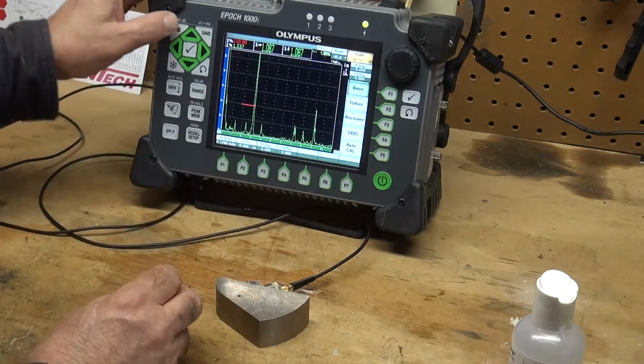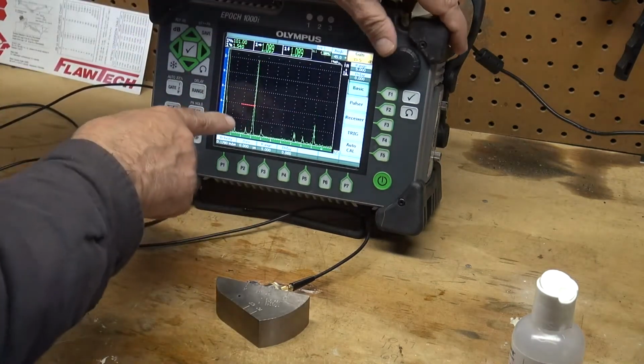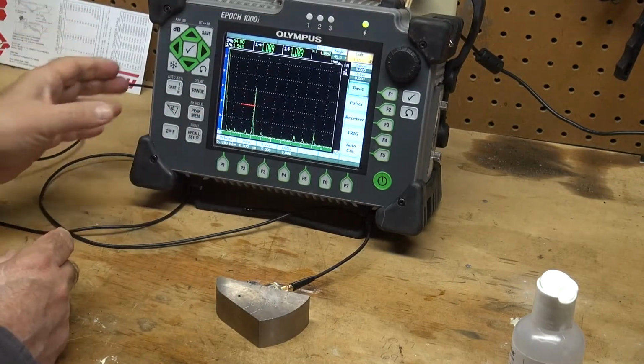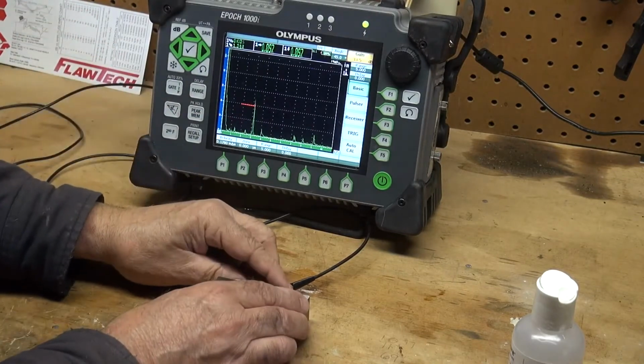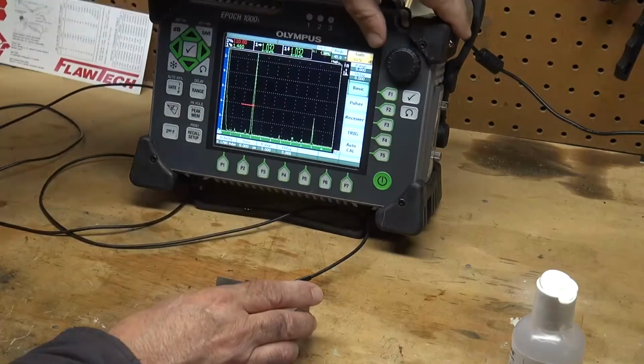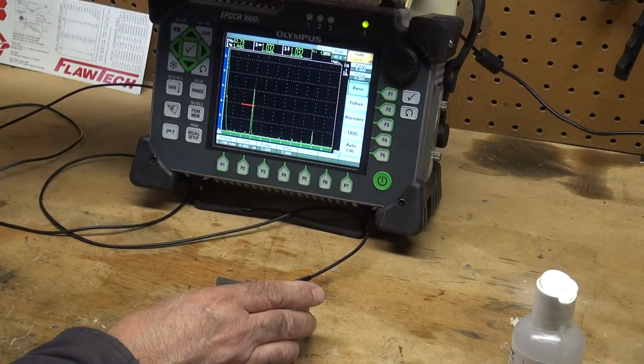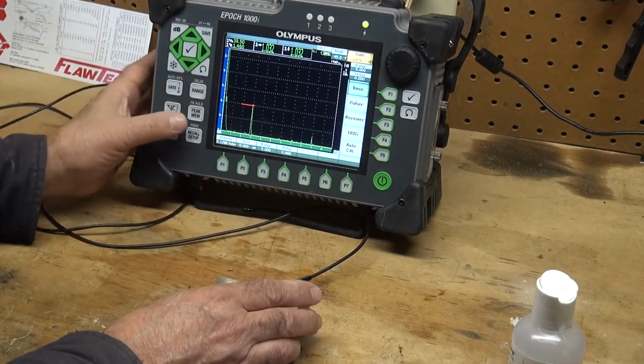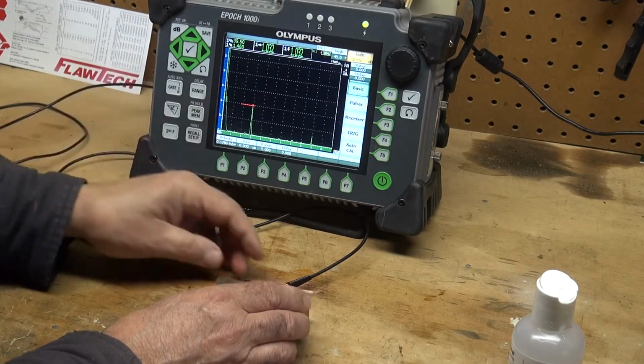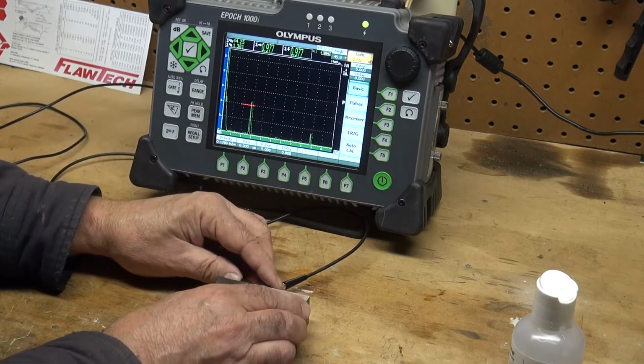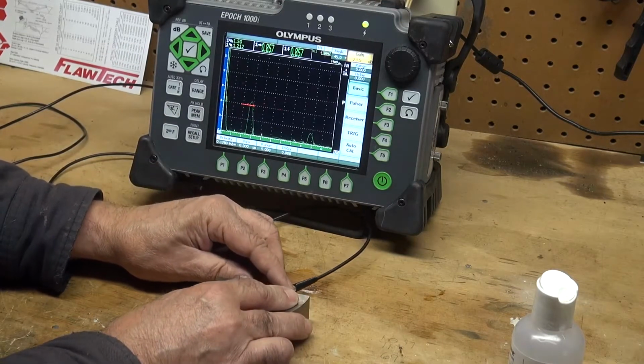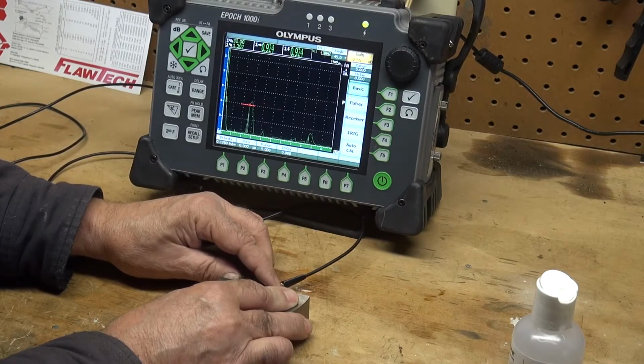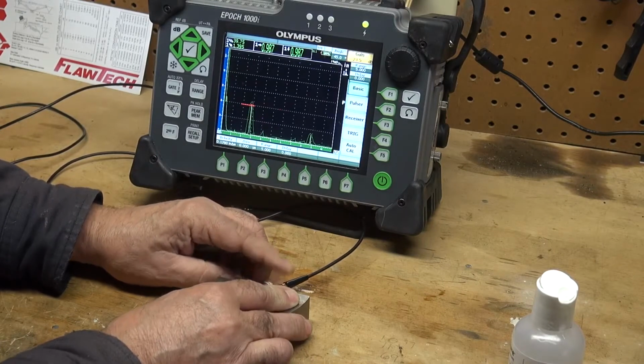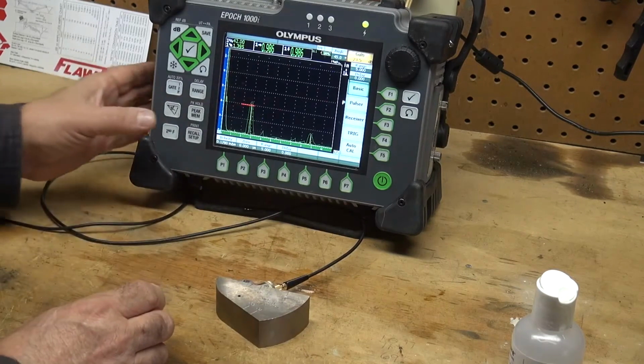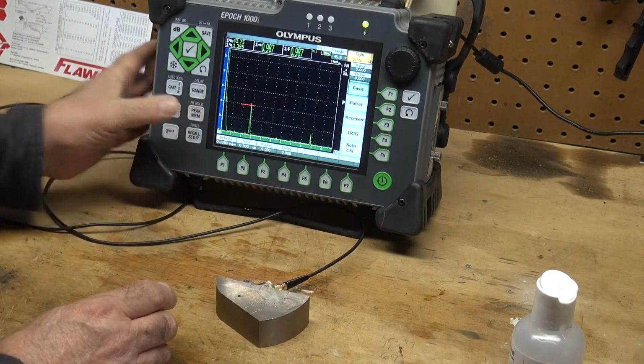So I want to take a little bit of dB out here to bring my 1 inch radius down to a manageable level where I can see it on my screen. Like take out some dB, and using the peak memory on this machine, I can slide that transducer back and forth and see where that signal peaks. And right there is the peak of my signal. So I'm going to turn off the peak memory.